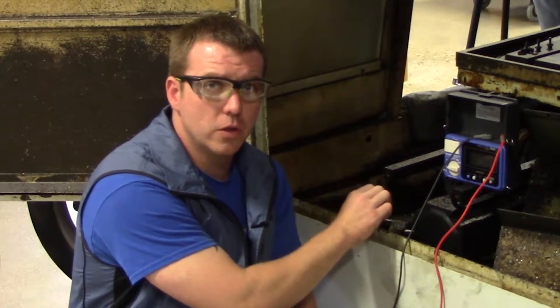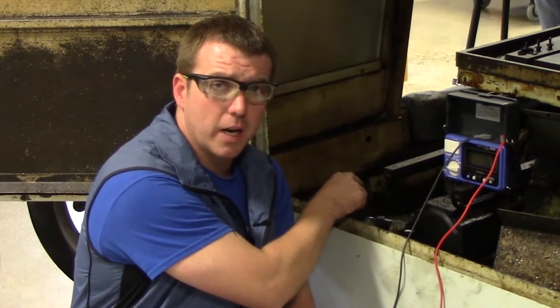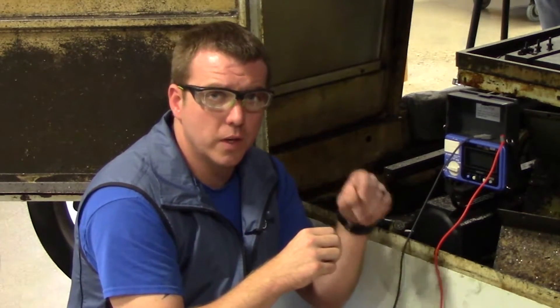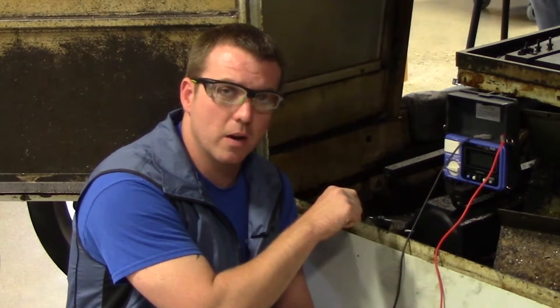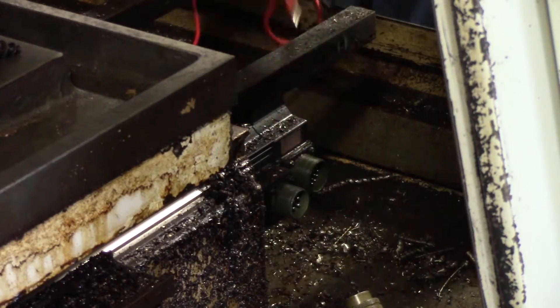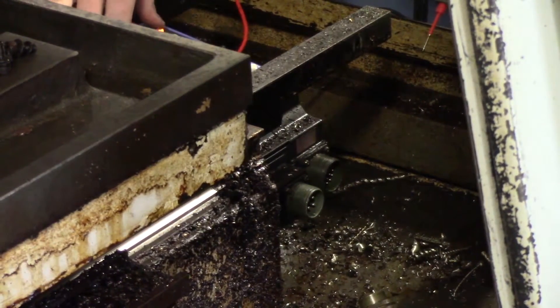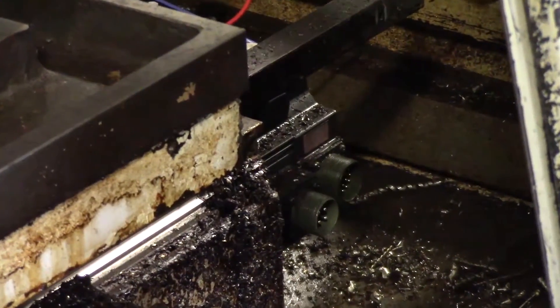So what we're going to do is from the cable from the cannon plug side we're going to go to D which is ground and then we'll check U V and W assuming we're still troubleshooting a problem and then if that were to be good then we'll go ahead and do D on the pin of the motor and we'll go U V W and check for a grounded motor. Let's go ahead and like I said we're pretending we're having a problem so I'm showing you guys how to troubleshoot this.